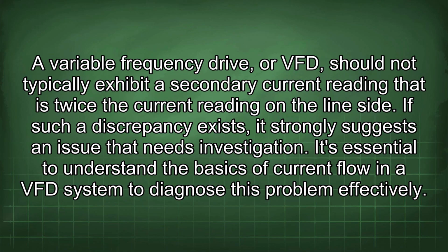A variable frequency drive, or VFD, should not typically exhibit a secondary current reading that is twice the current reading on the line side. If such a discrepancy exists, it strongly suggests an issue that needs investigation. It's essential to understand the basics of current flow in a VFD system to diagnose this problem effectively.